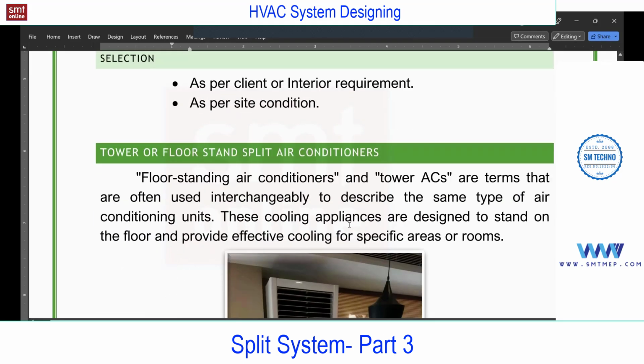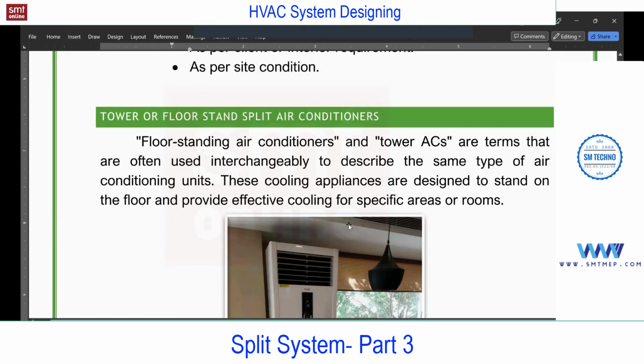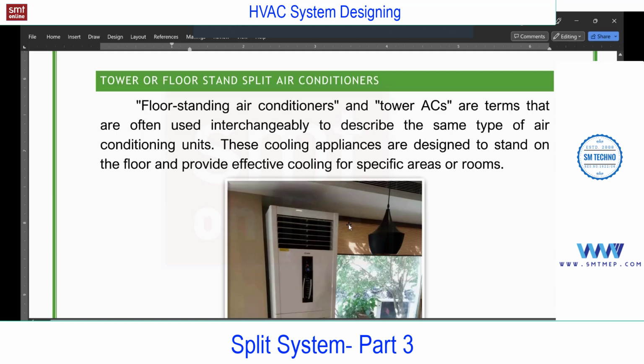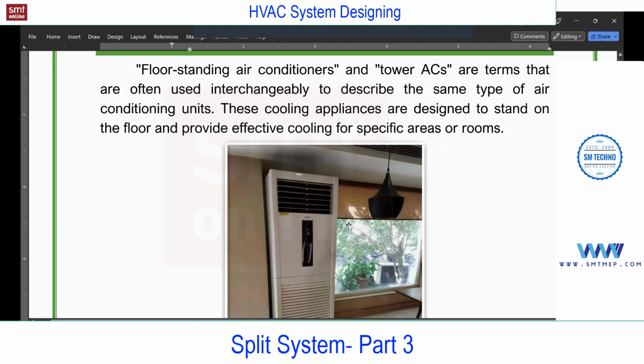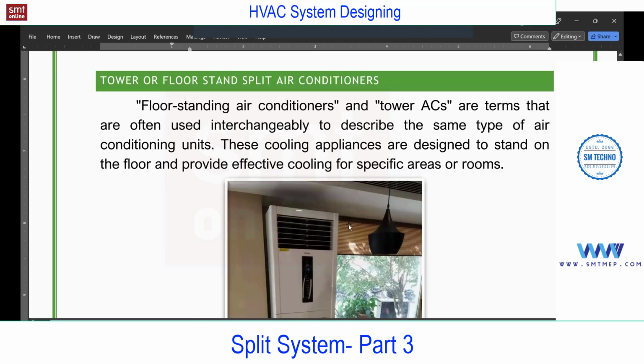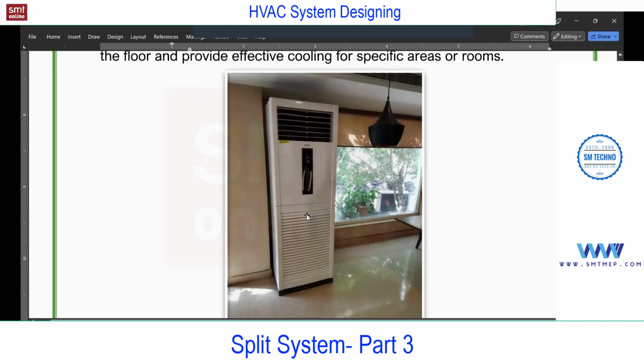We have one more, that is a tower or floor stand. So let me quickly complete this, because this is also the same type, means split only, but the type of FCU is different. So in some project, you may not get the clearance on the wall, or you may not get the clearance even in the false ceiling, because false ceiling also comes with some interior design with the lighting, etc. So they may not provide the clearance. In that case, we can go for this tower, you see. So remember, this is also connected to the outdoor unit. This is not like an air cooler.